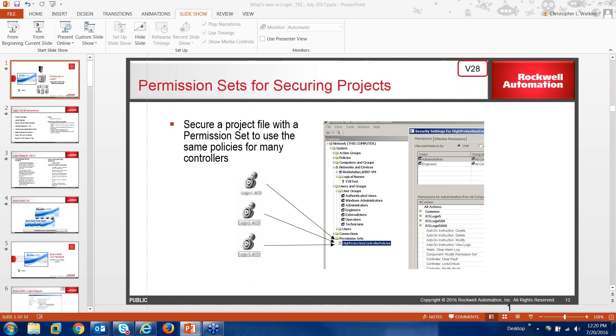Another security feature added is setting permissions for the different programs you have. With the appropriate policies in place, you can have someone take a look at permissions by product line or production level. The directory does not get modified whether it's one or a thousand controllers, but you do have the ability to create permissions by category. Previously, a logical name was created in the Factory Talk directory for each secured controller, requiring a new object every time. Now you have more flexibility when securing projects.